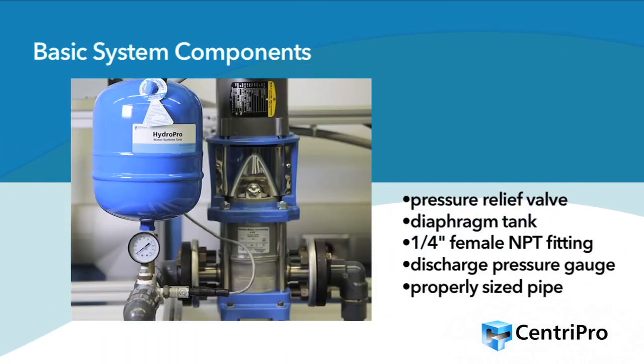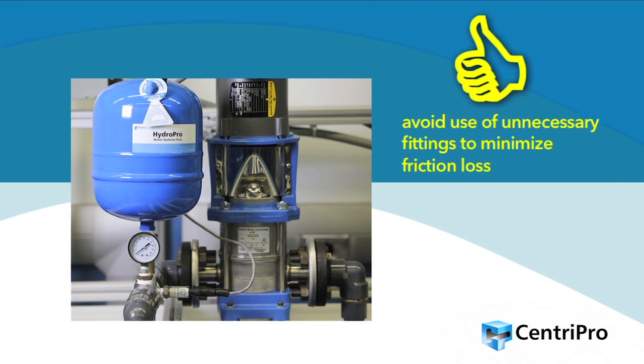A basic Aquavar SPD system should include a pressure relief valve, a diaphragm tank that is 20% of the total system capacity and set 20 PSI below the set point, a 1/4 inch female NPT threaded fitting for the pressure transducer, a discharge pressure gauge, and properly sized pipe that is not smaller than the pump discharge and/or suction connections. Rule of thumb: avoid the use of unnecessary fittings to minimize friction loss.